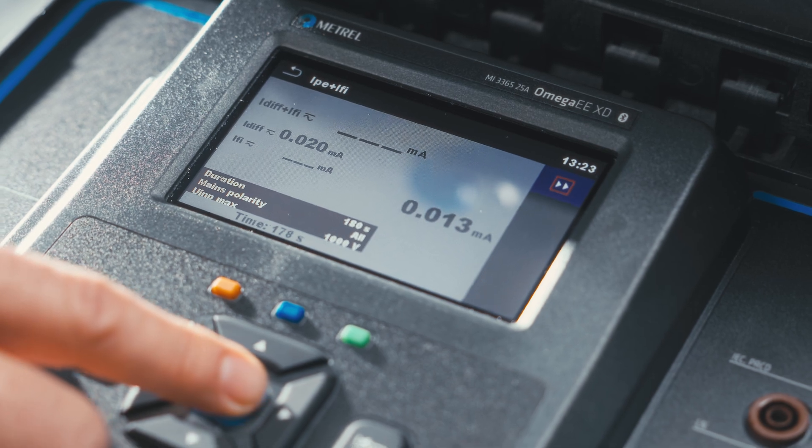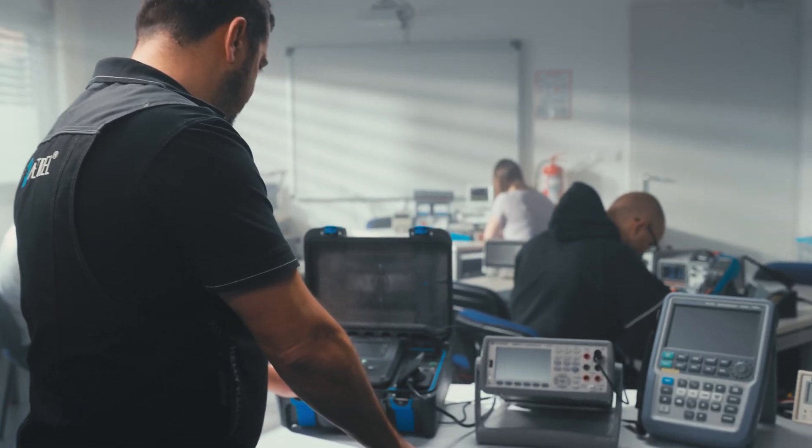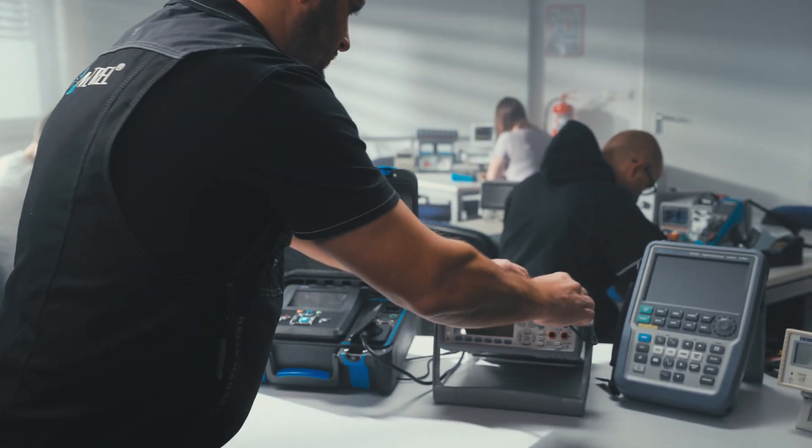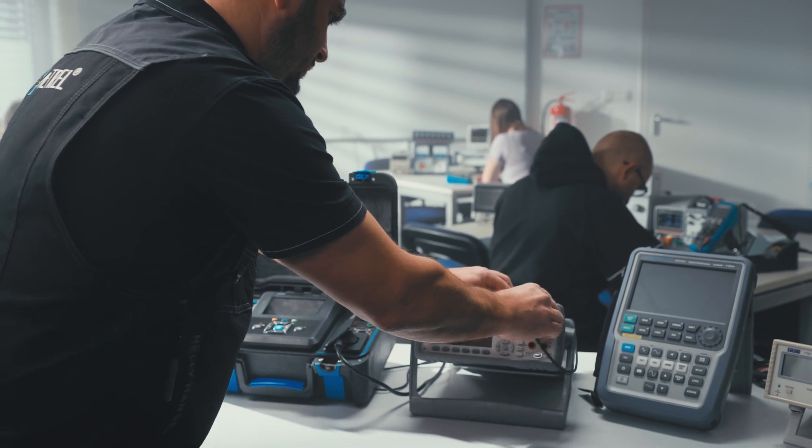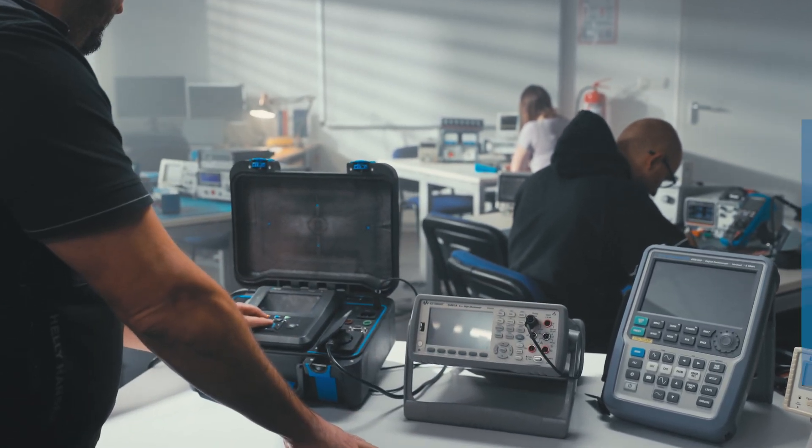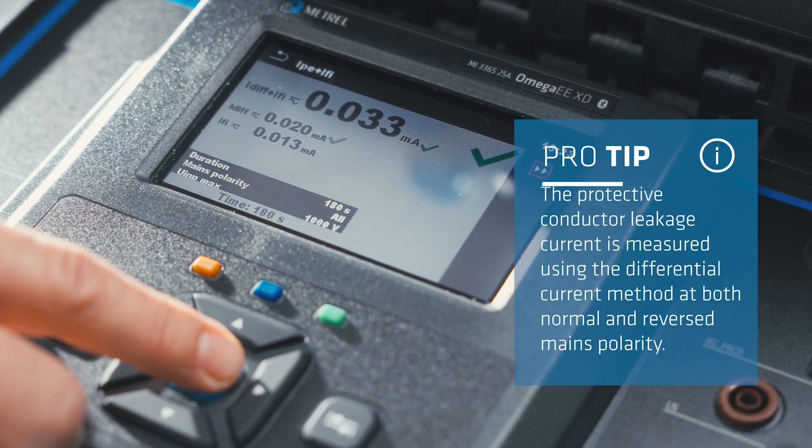The first step is evaluation of the protective conductor current without connecting the inputs through measuring the Differential Leakage Current IDIF.